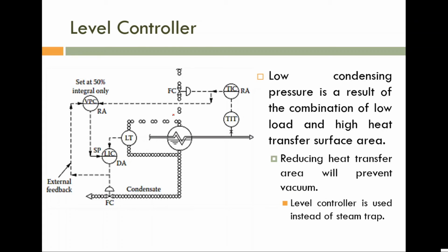So if you are able to avoid the sudden variation of heat transfer area, we can avoid the blown up problem. So here, compared to the first instrumentation, that is throttling of steam flow rate, in that particular instrumentation, the heat transfer area is 100%. The heat transfer area is fully available. But here, you can see that it is partially available.